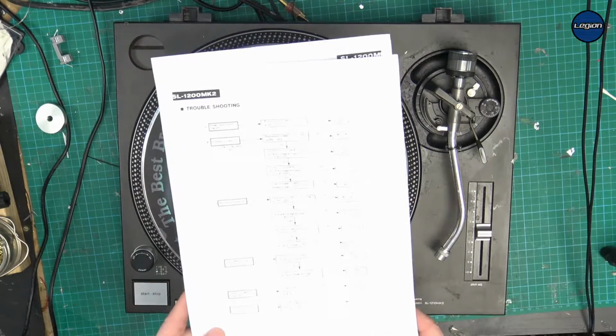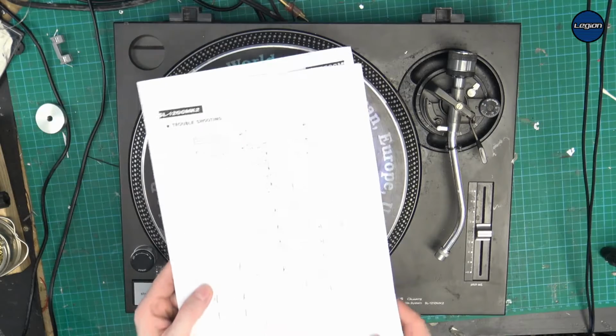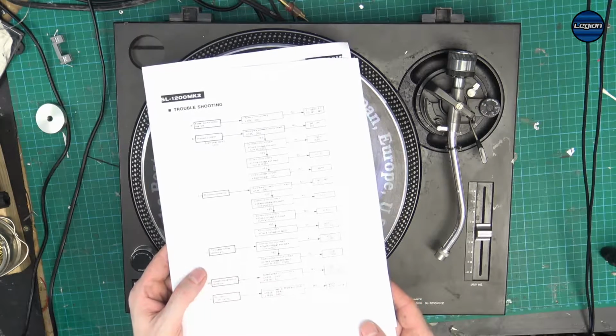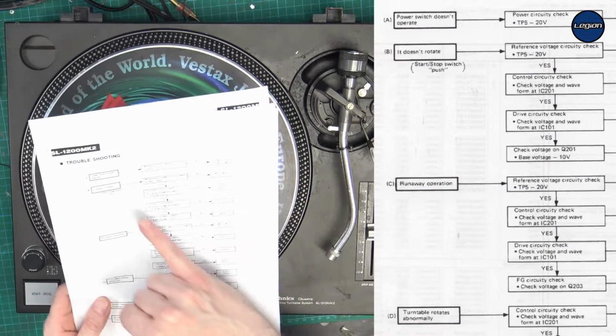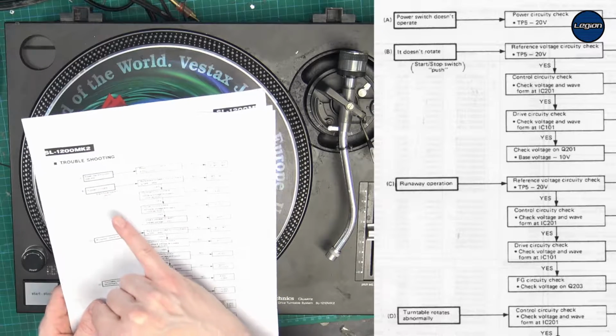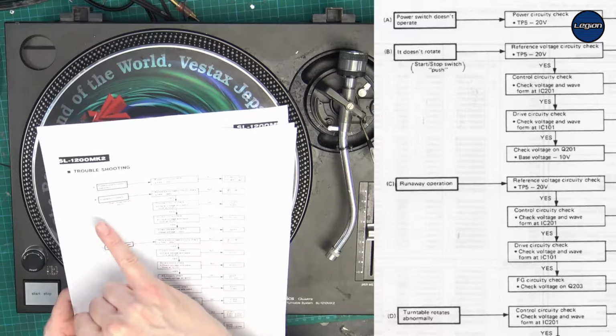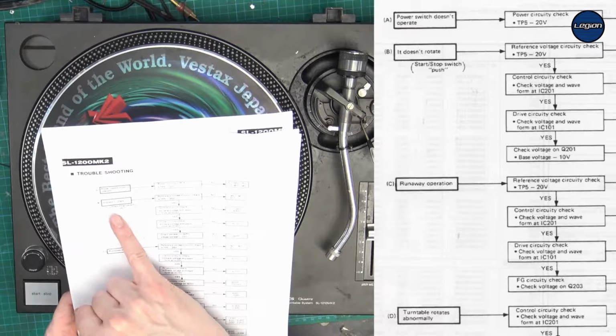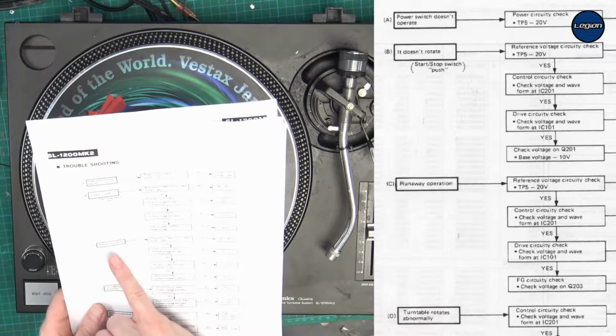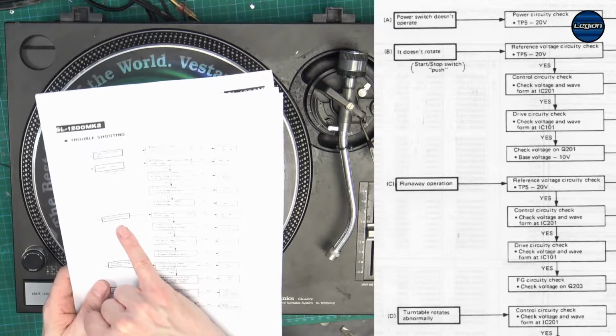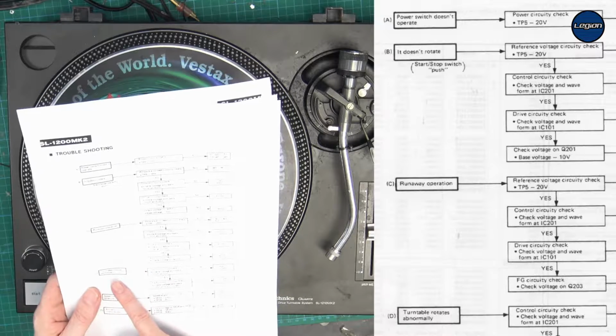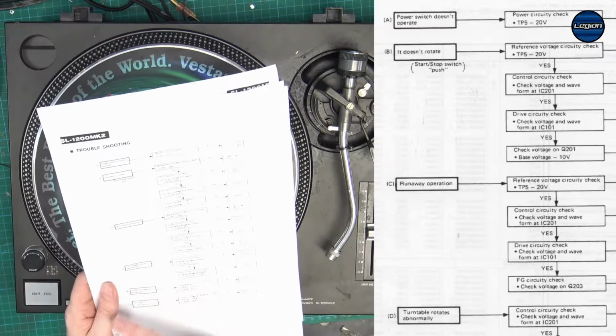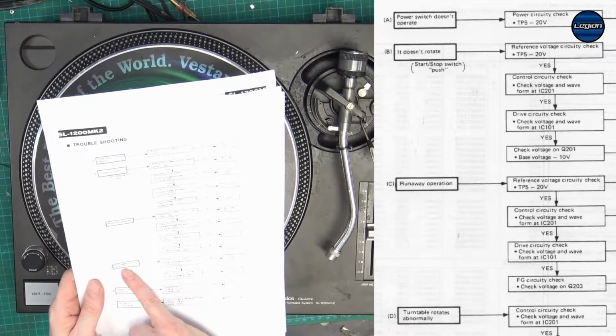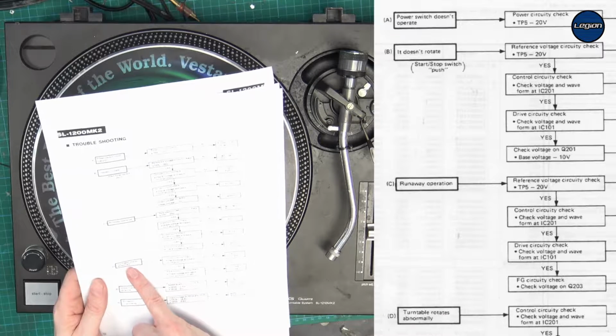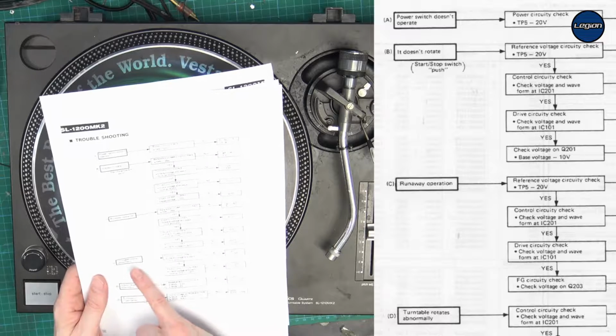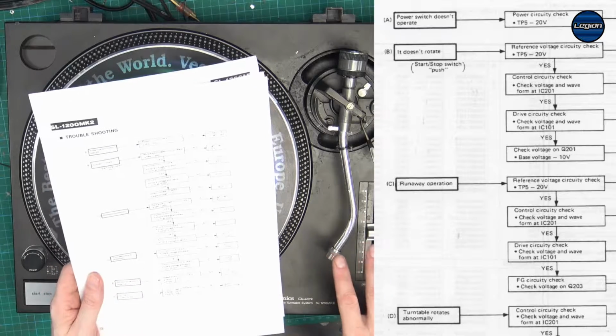So this is the printout that I'm using. I will show this on the screen in better quality. If we look down the troubleshooting, it says power switch doesn't operate. We know that's not the case. Doesn't rotate, it's not that one. Runaway operation, it's possibly runaway operation. Turntable rotates abnormally. Well, yeah, it's kind of doing that one as well, but abnormally would be kind of like wobbling, which happens when the pitch is bad or the pitch is not connected.